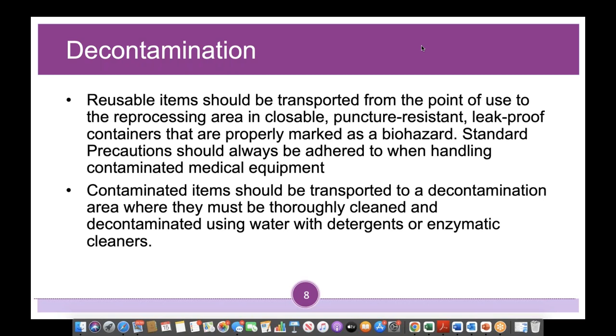Back to decontamination. Reusable items should be transported from the point of use to the reprocessing area in closable, puncture-resistant, leak-proof containers that are properly marked as biohazard. Standard precautions should always be adhered to when handling contaminated medical equipment.